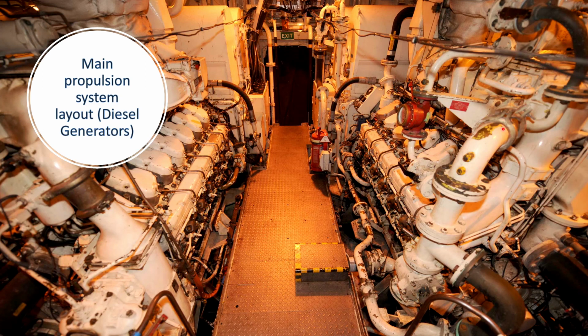In addition, the things were prone to oil leaks, and they weren't the best consumers of diesel, although they weren't too bad. Another feature of the upstairs diesels is that they need cooling. Although the diesels themselves are cooled by a freshwater loop, that fresh water is cooled with a seawater-freshwater intercooler. For the engine on our right — the starboard engine, since we're looking forward — that cooler is underneath the gangway we're standing on. For the engine on our left, the cooler is further to the left, out of shot. Those coolers receive water from the low pressure saltwater system, which is a feature of Type 23s that's quite good. It essentially circulates low pressure salt water to various pieces of machinery that require cooling, rather than relying on the high pressure saltwater system, which is left free for its main job: firefighting.